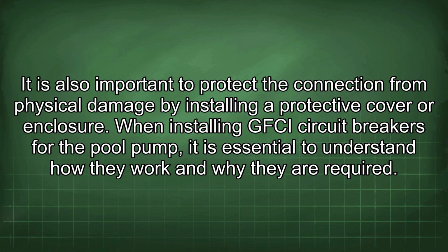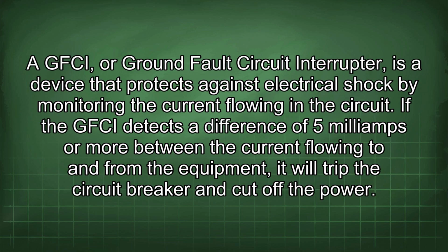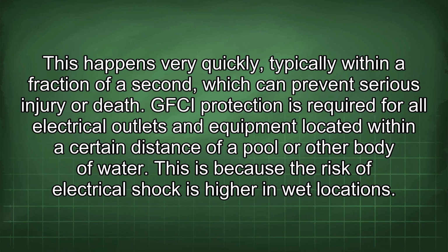When installing GFCI circuit breakers for the pool pump, it is essential to understand how they work and why they are required. A GFCI, or ground fault circuit interrupter, is a device that protects against electrical shock by monitoring the current flowing in the circuit. If the GFCI detects a difference of 5 mA or more between the current flowing to and from the equipment, it will trip the circuit breaker and cut off the power. This happens very quickly, typically within a fraction of a second, which can prevent serious injury or death.